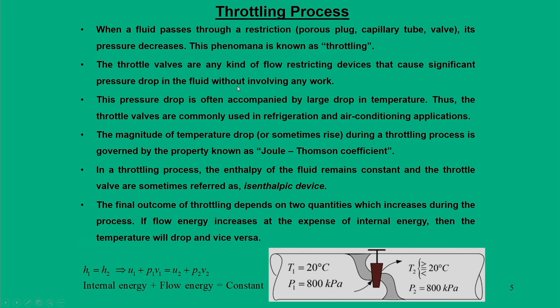Throttling valves are any kind of flow restricting device that causes a significant pressure drop of the fluid without involvement of any work. This pressure drop is normally accompanied by a temperature drop. That is why the throttling process is a common phenomenon and throttle valves are mainly used for refrigeration and air conditioning applications.